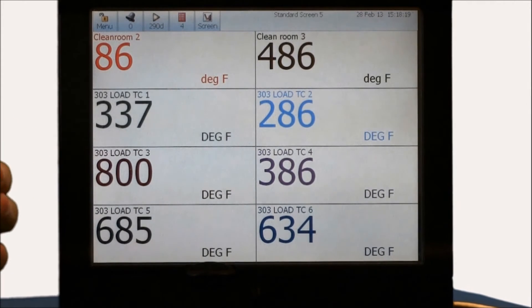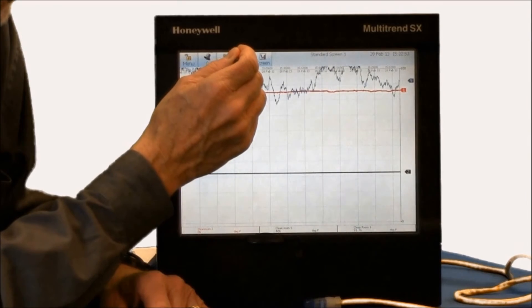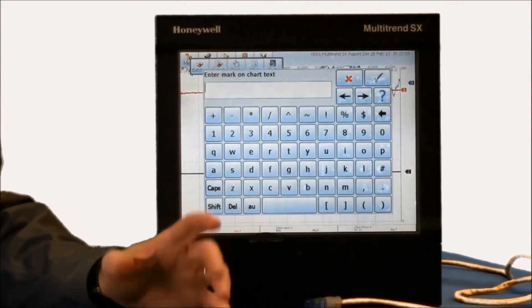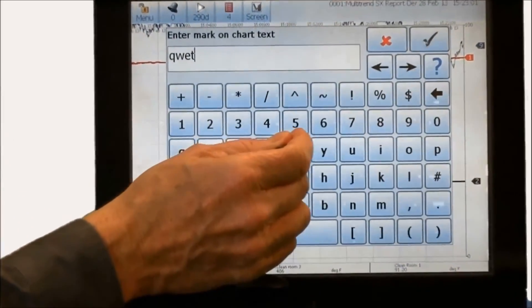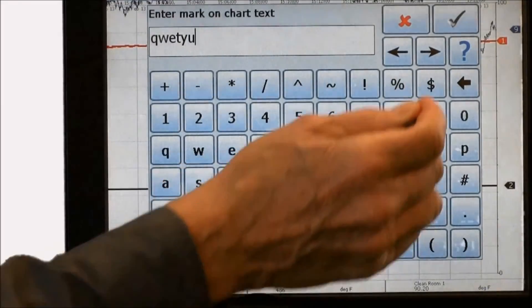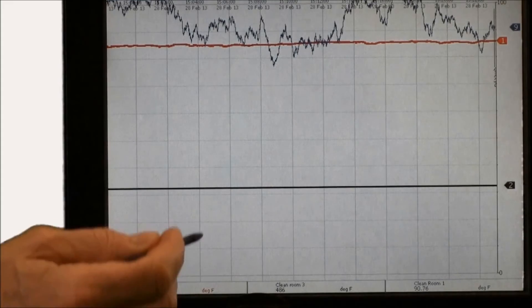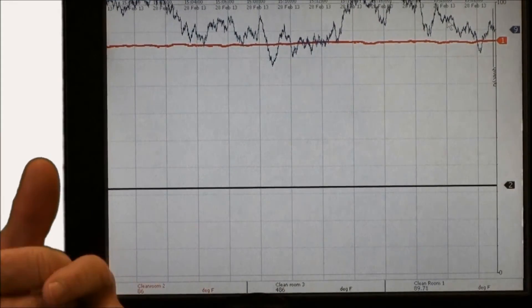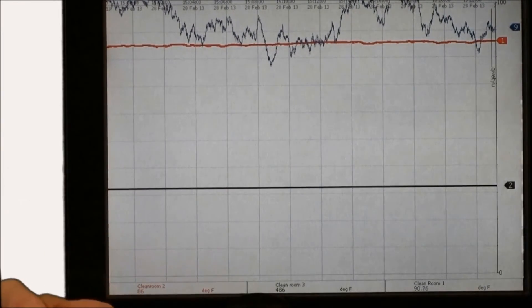Many paper recorder users are accustomed to making marks on their paper chart. That feature is also available in the paperless recorder by choosing the 'mark the chart' option, in which case a QWERTY keyboard comes up and you can type in a message — whether that's maintenance, alarm acknowledgement, or something else. Once you hit the check button, that actually marks the chart, and as the chart goes forward, you see that message on the chart. Wherever that's replayed on the recorder, months or years later, that's a permanent record as part of the chart.